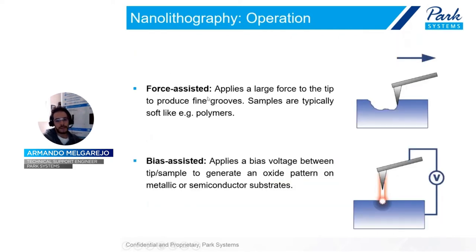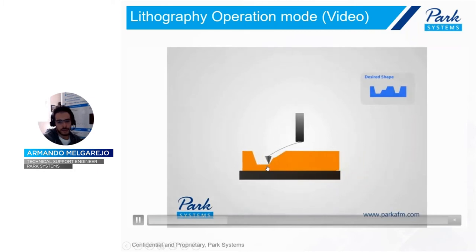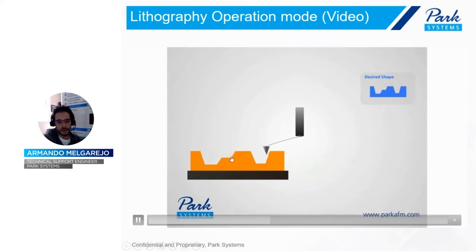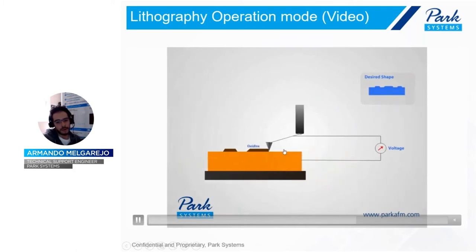We have two main classifications based on operation mode. The first is the force-assisted method, which consists of applying a certain amount of force to the sample to create defined grooves — typically on soft samples like polymers, as we can see in the image. The second option is the bias-assisted mode, which consists of applying a certain amount of voltage to create oxide patterns on the surface. The sample has to be able to generate oxide — like metallic or semiconductor substrates. You apply force or voltage, and depending on the amount, you create the desired shape or oxide patterns.